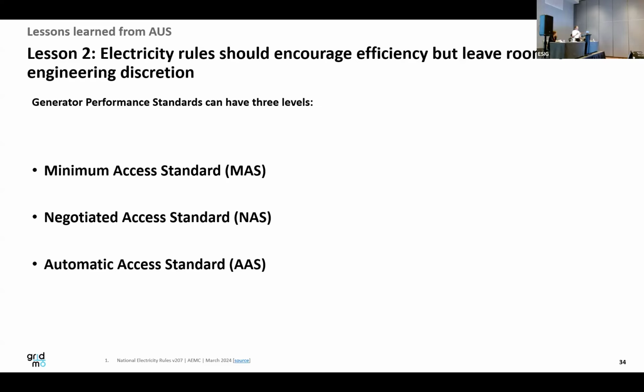Taking that example, it's not like here's the curve and that's what you've got to meet. We have 3 classes of the standard. We have the minimum access standard, which is if you don't do this, you don't pass go. That is the bare minimum of what you need to do as a generating system. Then we have the automatic access standard, which says if you do this or more, I'm not really going to ask any questions. Sounds great. And then you've got room to negotiate in the middle.